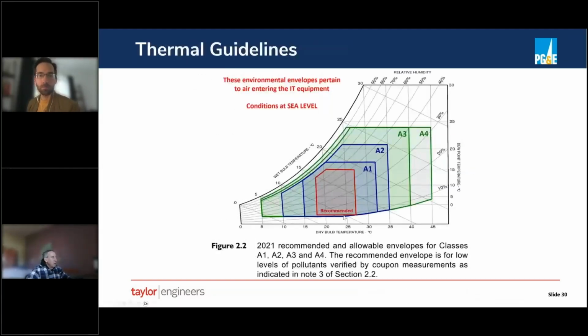So here's basically the same information depicted on a psychrometric chart. We have the recommended envelope, and then the A1, A2, A3, and A4. And the recommended, you can see, has both a dry bulb minimum, this is in SI units, and a maximum, an RH maximum of 70%, right? In this case, but also a dew point maximum of 15 degrees, and then a dew point minimum.